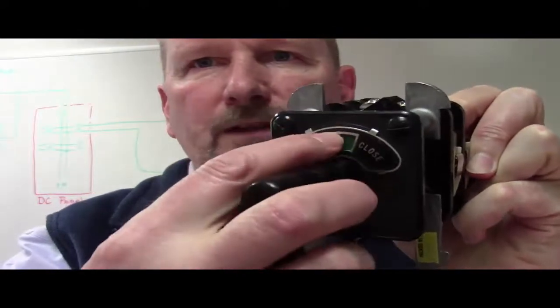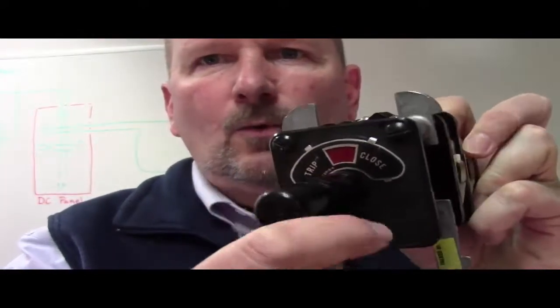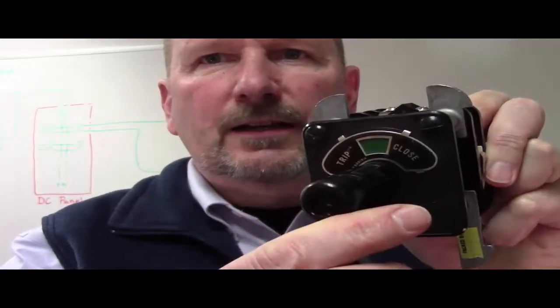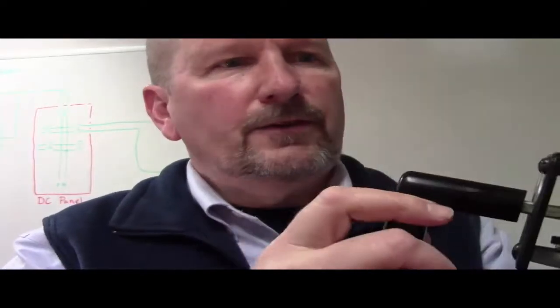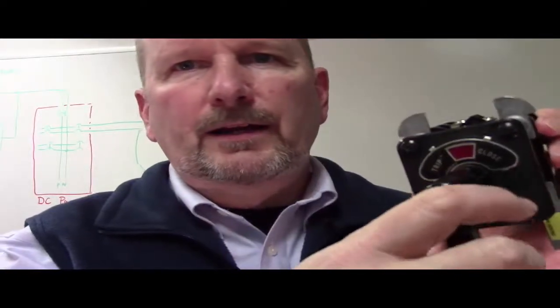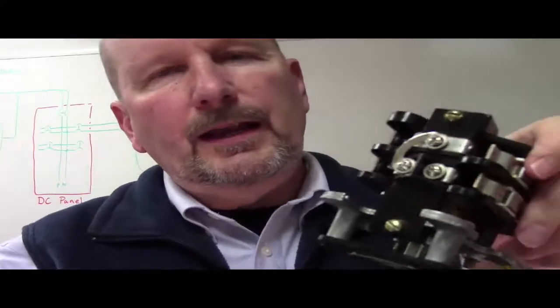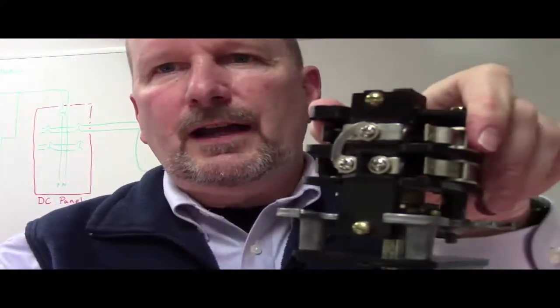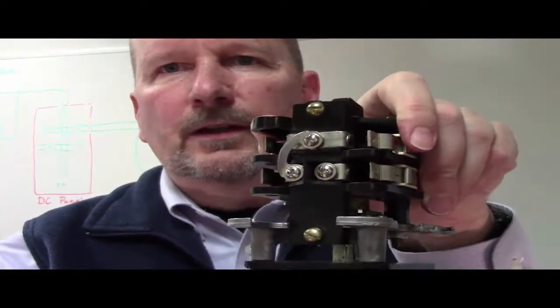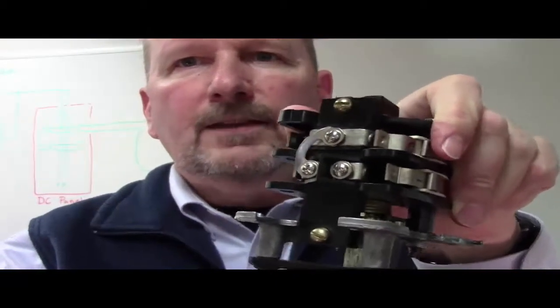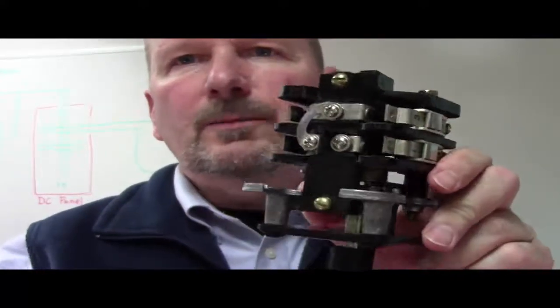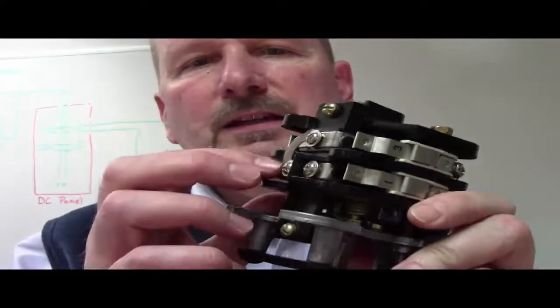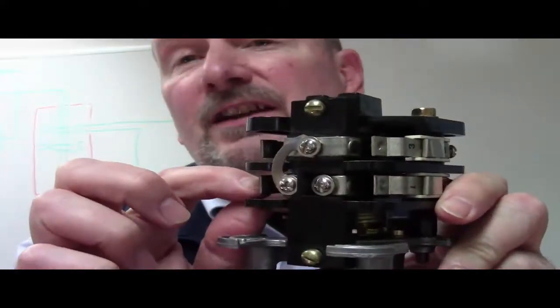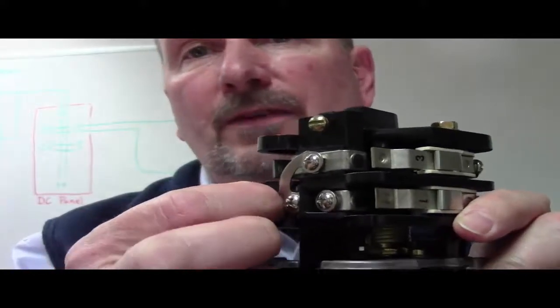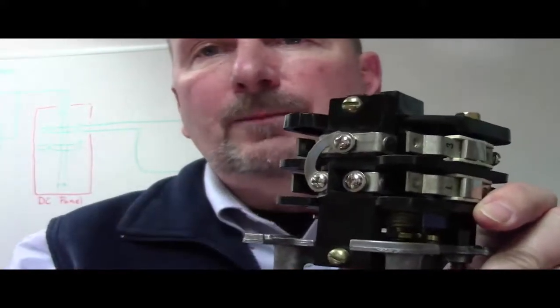On the front, you can see the control handle, and then there's a little slip contact right here that tells you what is the last function that it did, if it closed or opened. If you last closed it, it will be red. If you last opened it, it will be green. And as you're doing this, you will see that there are contacts right in here that close and do that. These contacts occasionally are called upon to break DC current. And you will see, or if you were here you would see, that they are nice and fat and have a lot of material on them and are not going to be damaged by having to break DC current.